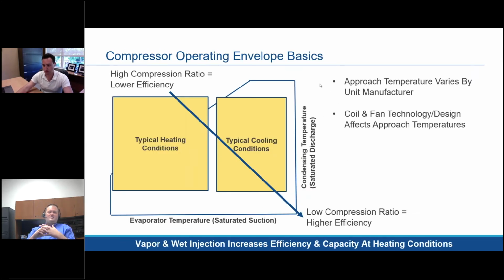And right now, this is kind of the basic operating envelope for a compressor. Like I said, on the x-axis you have your saturated suction or evaporator temperature. On the vertical axis you have your condensing temperature, saturated discharge. Typical cooling conditions are the more low compression ratio conditions. Then we have your typical heating conditions up in the left.